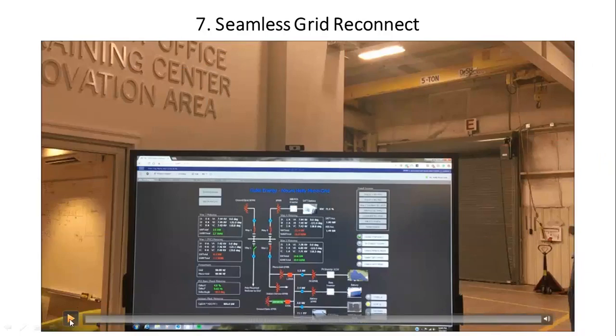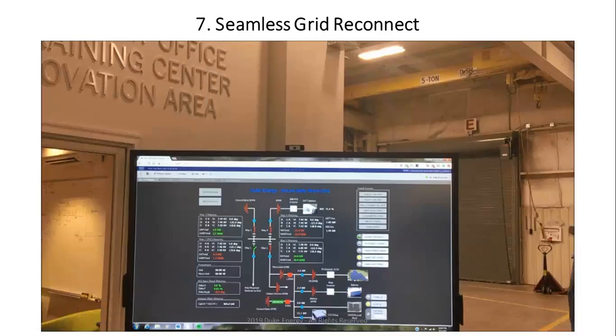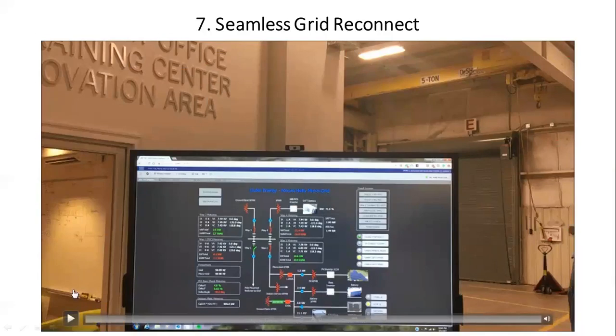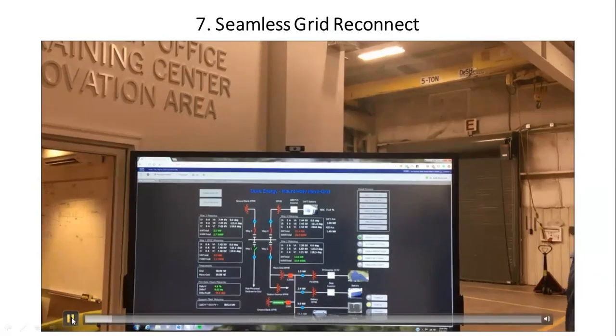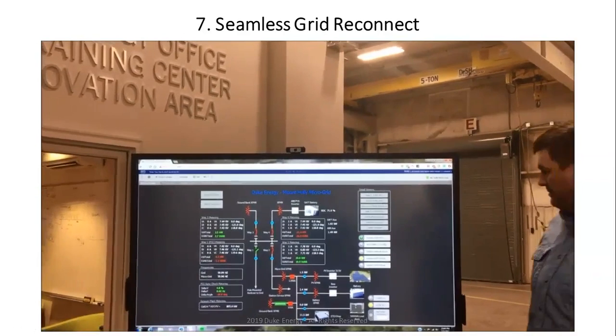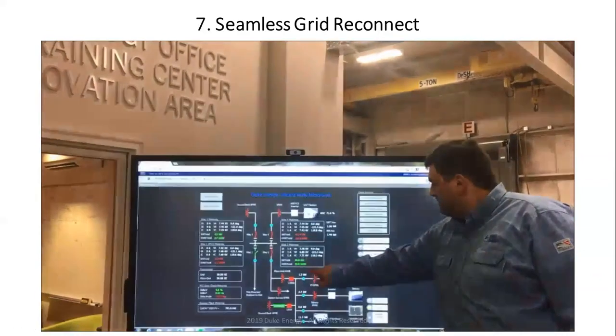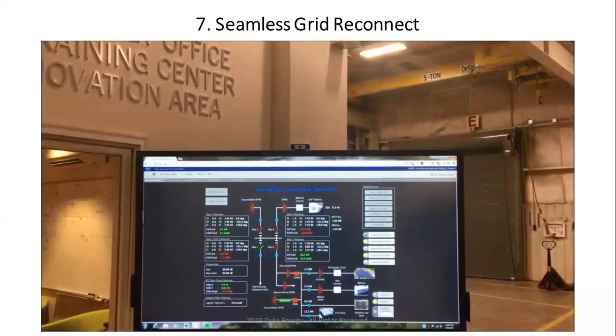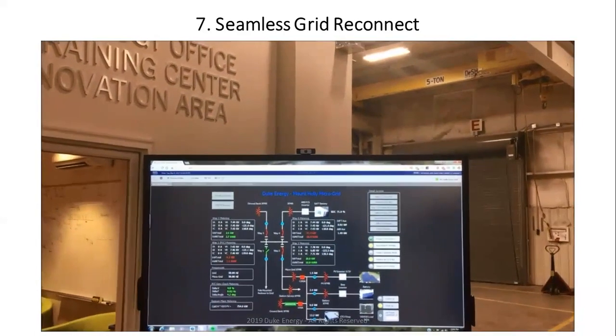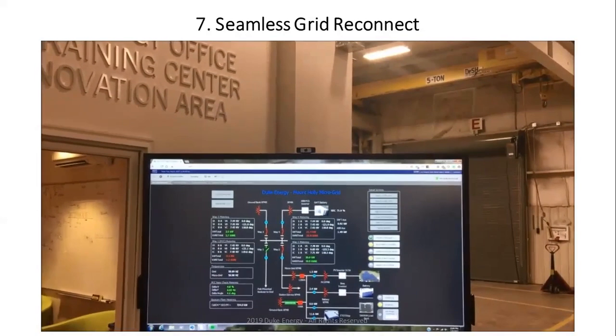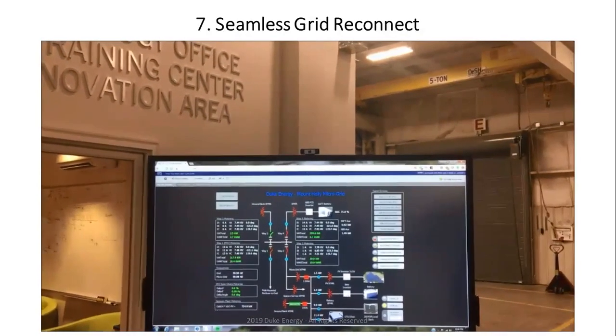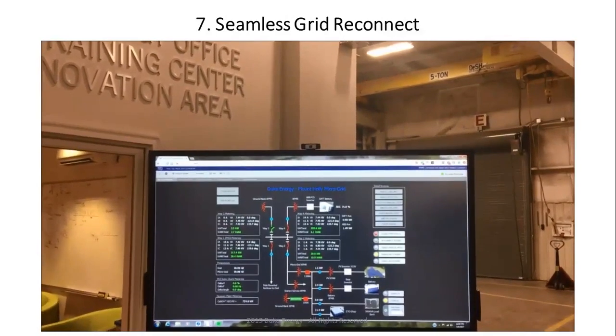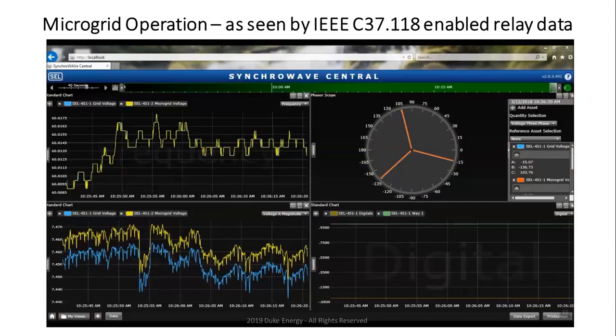So if you ever wanted to see how long that takes, you can take a look at this stuff. Sometimes it's anywhere between 2 and 6 or 2 and 8 seconds. If you look on the bottom left, you're going to see 2 green and 1 red. That's our delta V, delta F, and delta angle. So you can see right now that during the grid synchronization, the battery is going to bring all of these 3 into green. And there's a 2-second update on this particular screen. So you're going to see the grounding transformer open, actually in reality, after the wave 1. So as you can see, there was no voltage dip. We didn't lose any lights, et cetera. So you can see that it is seamless.